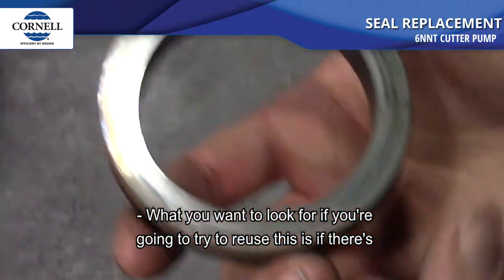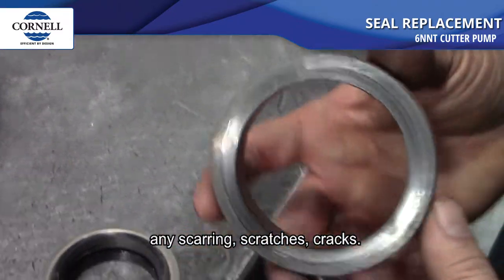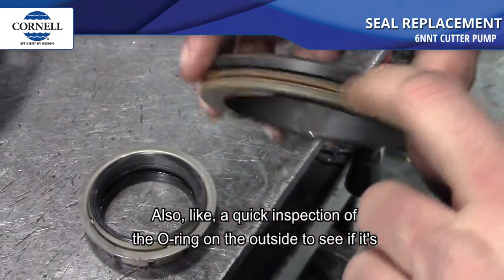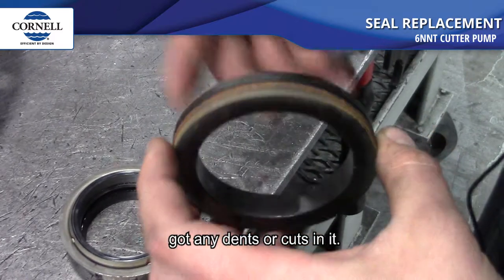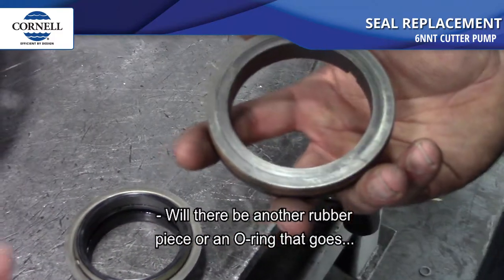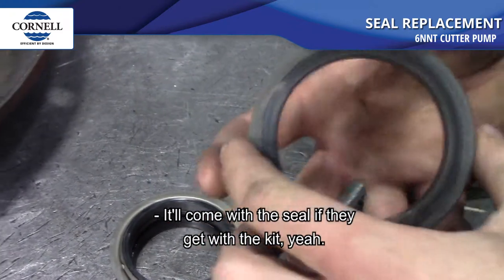What you want to look for if you're going to try to reuse the seal is any scarring, scratches, or cracks, and also a quick inspection of the o-ring on the outside to see if it's got any dents or cuts in it. It'll come with the seal if they get with the kit, yeah.